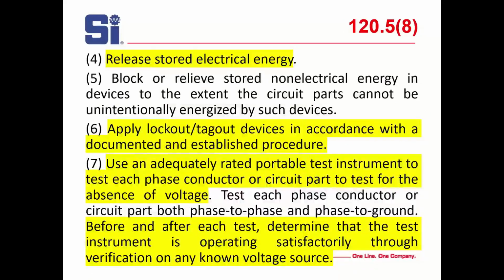Release stored energy. You have to take a grounding stick and be sure that any energy that may be stored by capacitors or inductors, anything of that nature, is relieved. Block or relieve stored non-electrical energy so the equipment cannot unintentionally be energized by such devices. Well, if you do de-energize those devices, that's very slim, but things happen. Apply lockout tagout devices in accordance with documents and established procedure. You should have one, I hope.